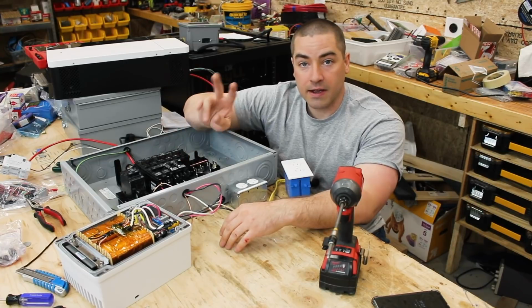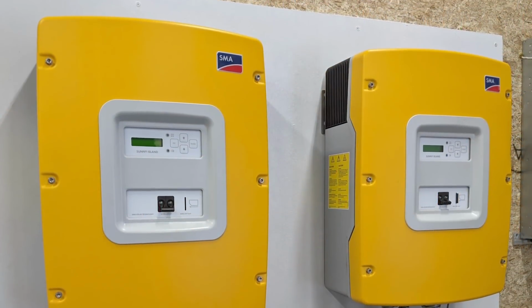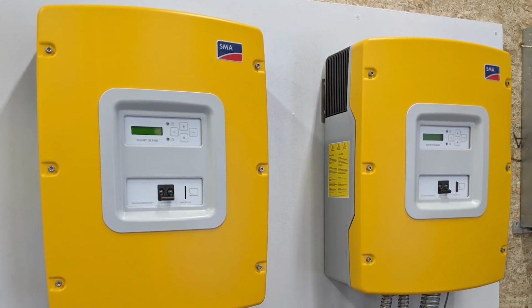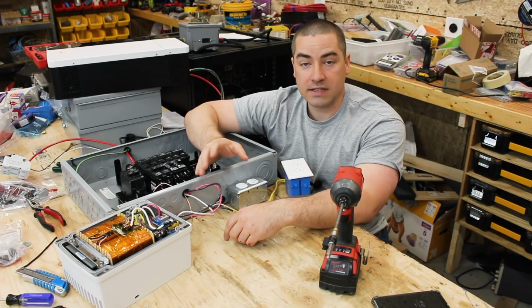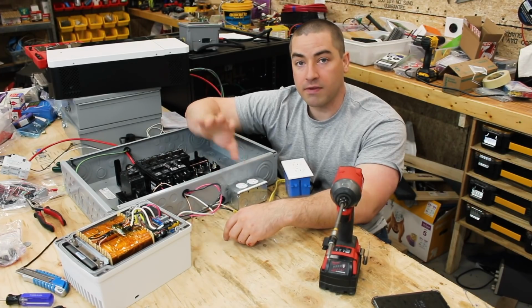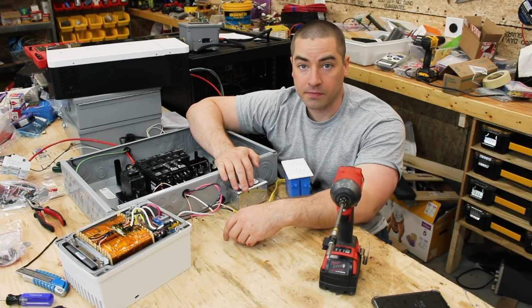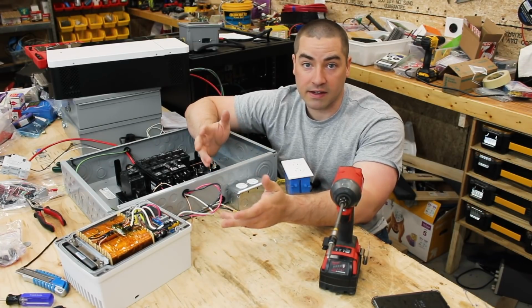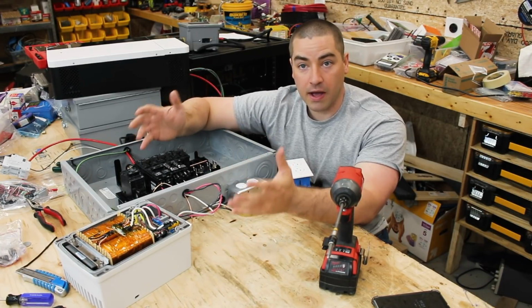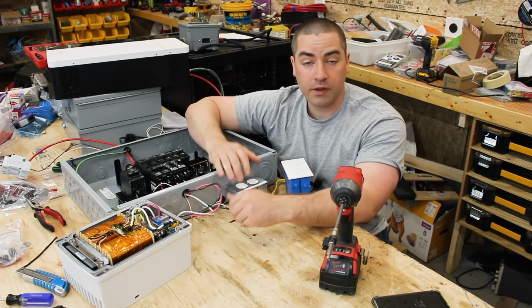So in my case, I have two SMA Sunny Island inverters, each one is about 6,000 watts. So I max out at 6,000 watts per phase. Even if the other phase has nothing on it, that's it, that's all I have then is 6,000 watts, even though the combined total of the two inverters is 12,000 watts.